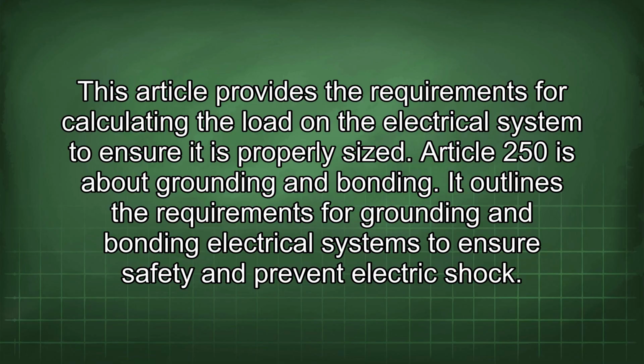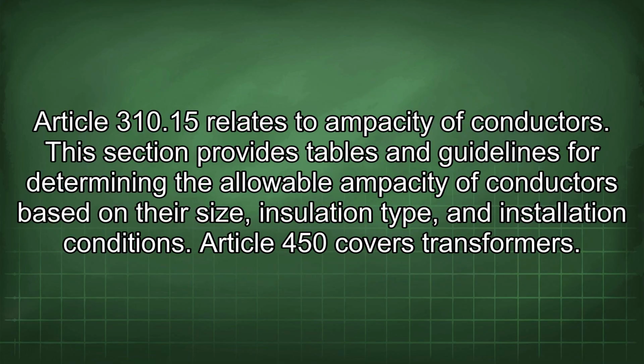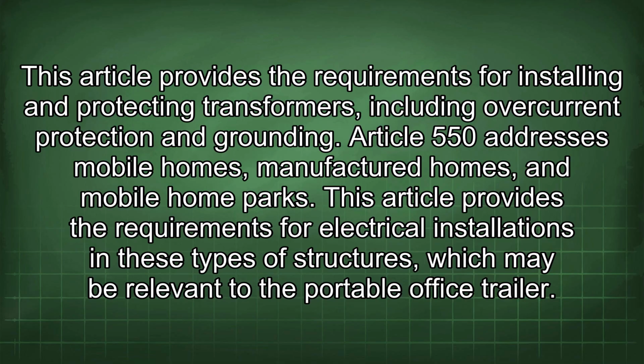Article 250 is about grounding and bonding. It outlines the requirements for grounding and bonding electrical systems to ensure safety and prevent electric shock. Article 310.15 relates to ampacity of conductors. This section provides tables and guidelines for determining the allowable ampacity of conductors based on their size, insulation type, and installation conditions. Article 450 covers transformers. This article provides the requirements for installing and protecting transformers, including overcurrent protection and grounding.